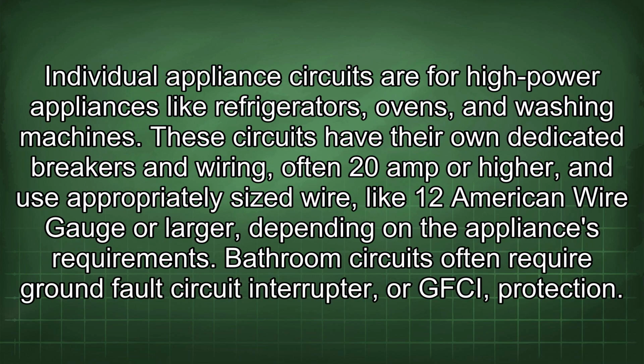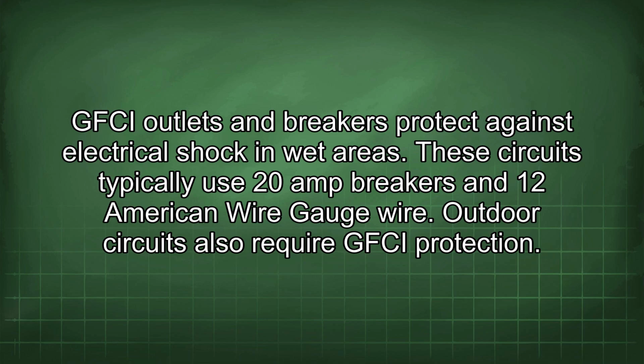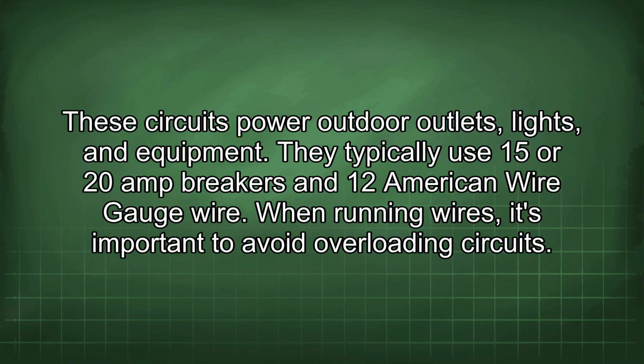Individual appliance circuits are for high-power appliances like refrigerators, ovens, and washing machines. These circuits have their own dedicated breakers and wiring, often 20 amp or higher, and use appropriately sized wire, like 12 American wire gauge or larger, depending on the appliance's requirements. Bathroom circuits often require ground fault circuit interrupter, or GFCI, protection. GFCI outlets and breakers protect against electrical shock in wet areas. These circuits typically use 20 amp breakers and 12 American wire gauge wire. Outdoor circuits also require GFCI protection. These circuits power outdoor outlets, lights, and equipment. They typically use 15 or 20 amp breakers and 12 American wire gauge wire.